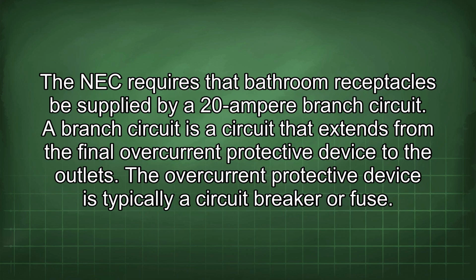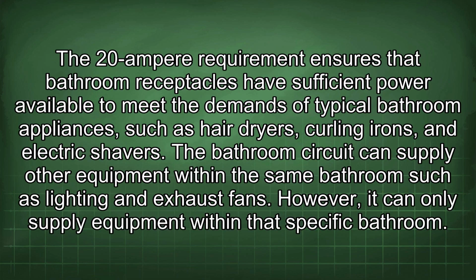The NEC requires that bathroom receptacles be supplied by a 20 ampere branch circuit. A branch circuit is a circuit that extends from the final overcurrent protective device to the outlets. The overcurrent protective device is typically a circuit breaker or fuse. The 20 ampere requirement ensures that bathroom receptacles have sufficient power available to meet the demands of typical bathroom appliances such as hair dryers, curling irons, and electric shavers. The bathroom circuit can supply other equipment within the same bathroom such as lighting and exhaust fans. However, it can only supply equipment within that specific bathroom.